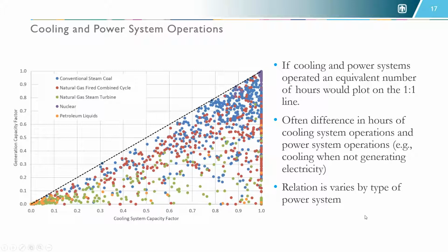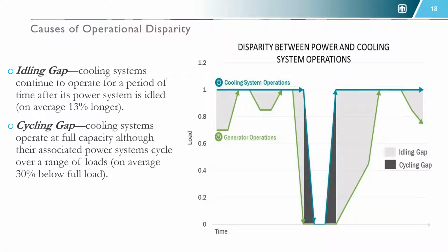Next slide. We dug into this much deeper to understand what's going on. To help explain what we've learned, we drew this schematic on the right - think of this in terms of a few days or weeks of operations, with a generator and boiler connected to a single cooling system. The green line is the operations of the generator as percent of full capacity, and the blue line is the cooling system's operations as percent of full capacity. The generator will vary depending on the kind of system and how the load is varying.